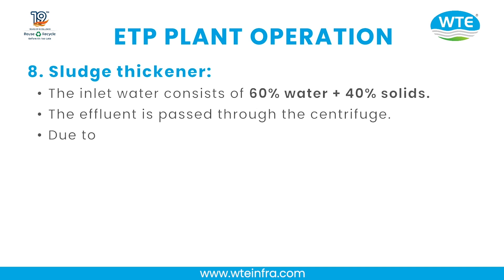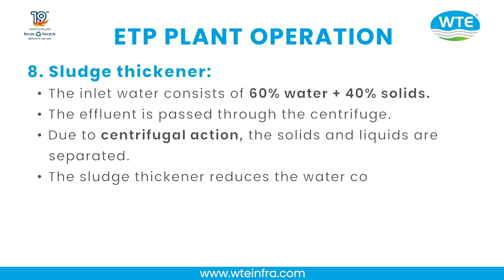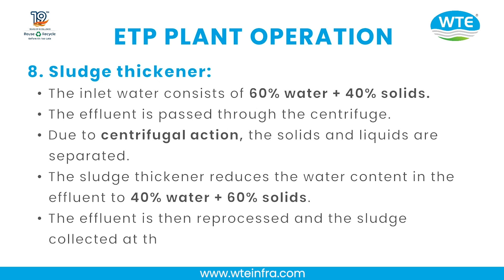Step 8 — Sludge Thickener: The inlet water consists of 60% water and 40% solids. The effluent is passed through a centrifuge; due to centrifugal action, solids and liquids are separated. The sludge thickener reduces the water content so the effluent becomes 40% water and 60% solids. The effluent is then reprocessed and the sludge is collected at the bottom.